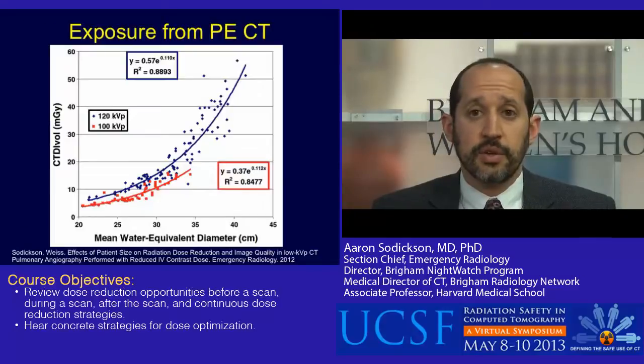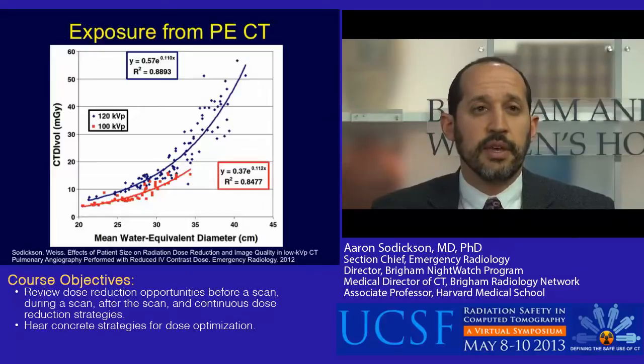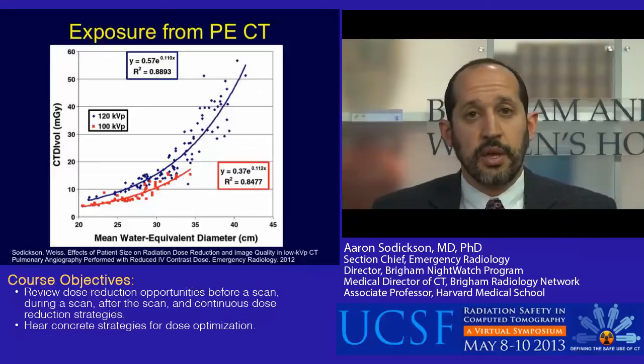Here's that data that I showed a little bit earlier, but now you can look at the red dots, which are the scans at 100 kV, and you see that in patients that are small enough here, we see that 33% overall dose reduction from using this technique.